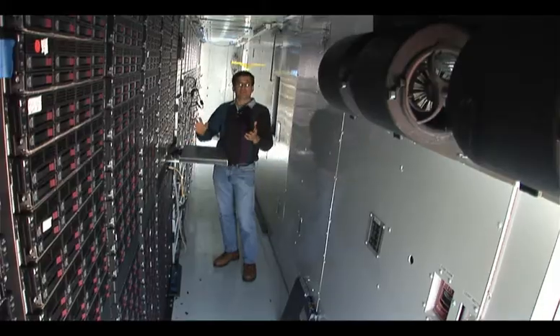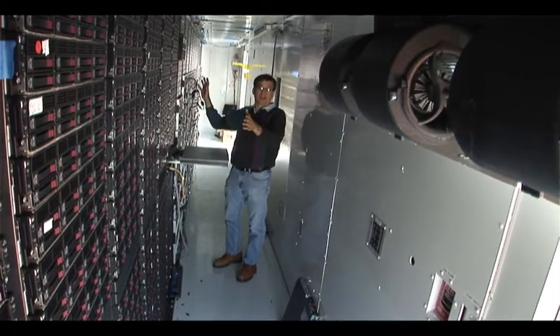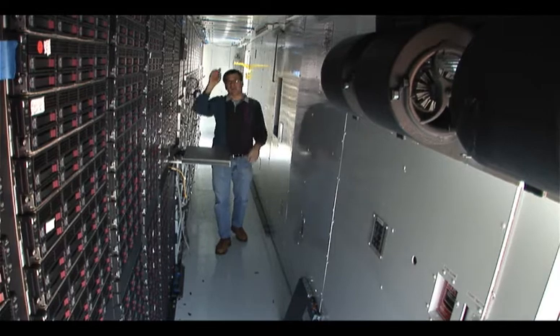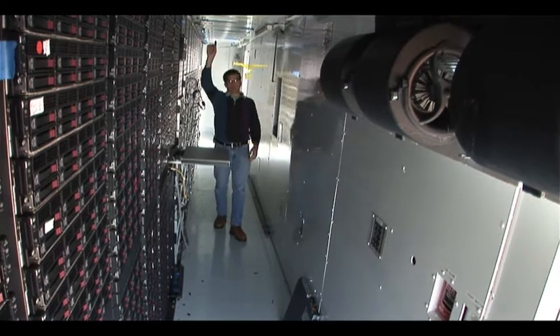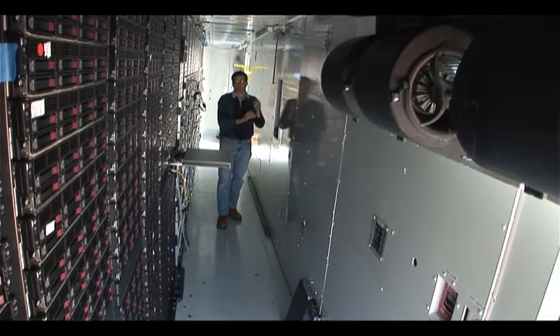The cooling efficiency is also because we have six discrete zones spread across the 22 racks. Each of the zones have air temperature sensors, water sensors, and pressure sensors, so we always lower the fan power to the least amount.